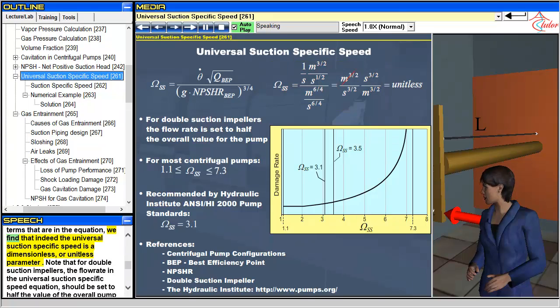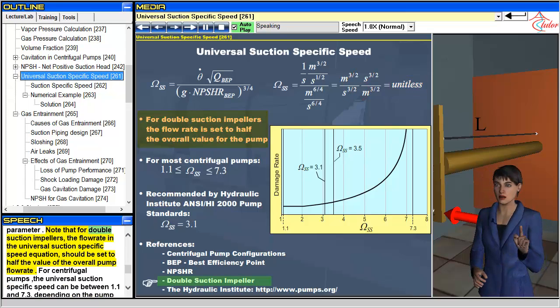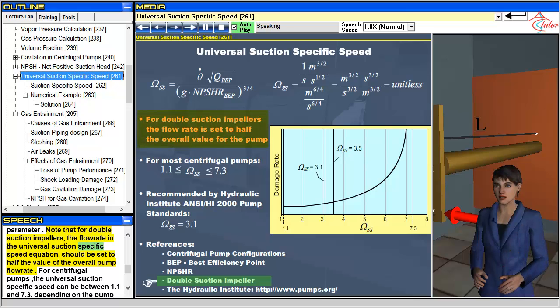we find that indeed the universal suction-specific speed is a dimensionless, or unitless parameter. Note that for double suction impellers, the flow rate in the universal suction-specific speed equation should be set to half the value of the overall pump flow rate.